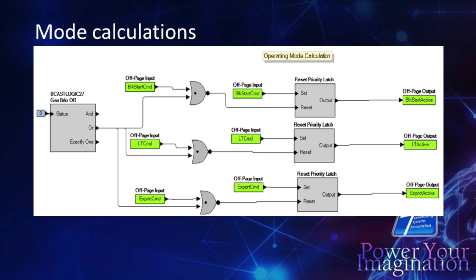Some more logic of how we did mode calculations of which one we're going to do. We had to know when the gen breakers were closed and to allow us to go into whichever mode we were going to go into. And then we can do the breaker statuses for the group breakers. And one issue we found with these group breakers: I typically do a system and we recommend station batteries as the power to the breakers, because if you have no power, you can't open or close breakers. These are not that way, they're AC powered.